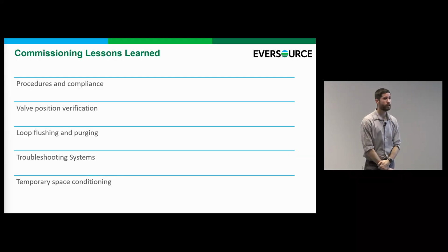Loop flushing and purging—the biggest issue I've seen on our system is air. There's a flushing procedure, but there's always a little entrained air in these systems, and getting it out is extremely important because it can shut down customer systems. You get a trouble call, you purge the air, and you start them back up. Definitely a step you don't want to shortcut or miss.